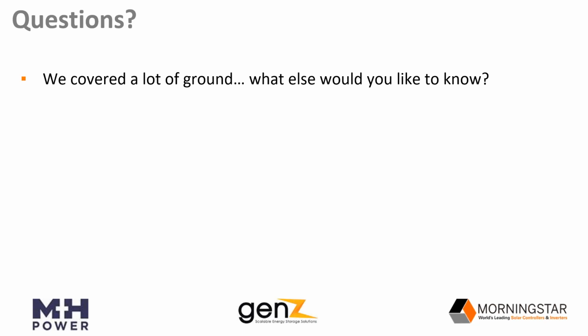All right. Here's a question from Pedro. Can you connect the 12-volt genZ range in series? Yep, very tricky question, Pedro. The only limitation we've got is the BMS that we've picked. The problem is not so much with discharging, but when it comes to charging, the BMS that we've picked doesn't really balance the cells properly when you put the two in series. So that's the only limitation we've got with the current BMS. Okay, very good. Thanks for that question. Thanks for the answer.